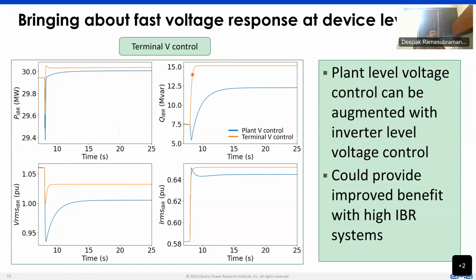Because at the end of the day, the transmission planner and the operator are interested in what is coming out from the plant. As long as the characteristics that come out of the plant meet the requirements that we lay out, which could be structured to provide this kind of characteristic, it shouldn't really matter whether it is at the plant level or the inverter level. The only reason for bringing out the plant level and inverter level classification in this entire presentation is to try and tie it to how things are being done today in the field.